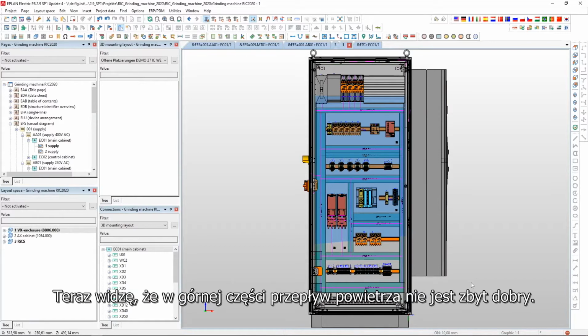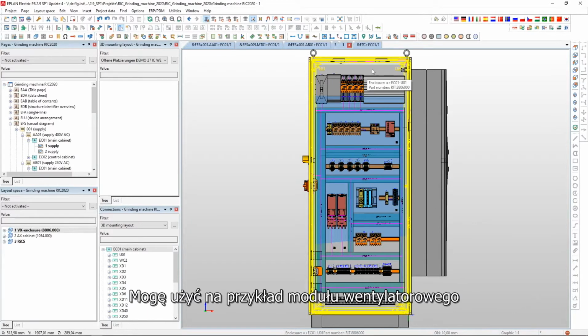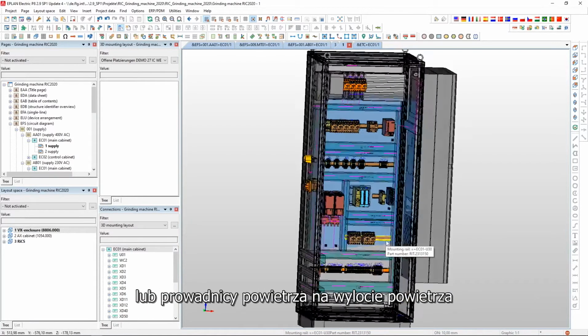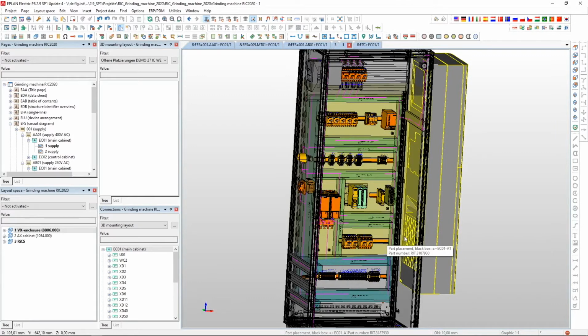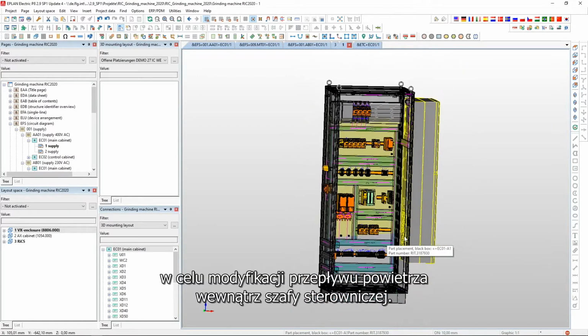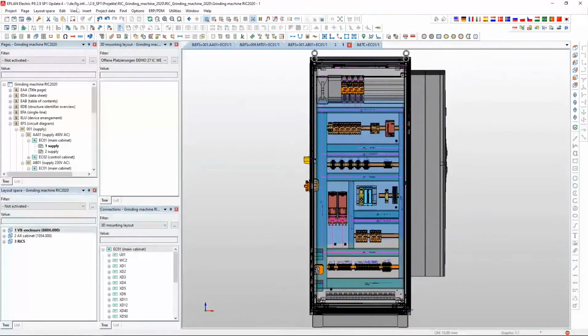Now I can decide - here on the top, the airflow is not very good. I can use a fan unit, for example, or I can use an air plate here on the air outtake to modify the airflow inside the enclosure.